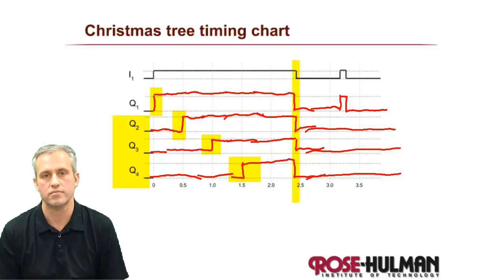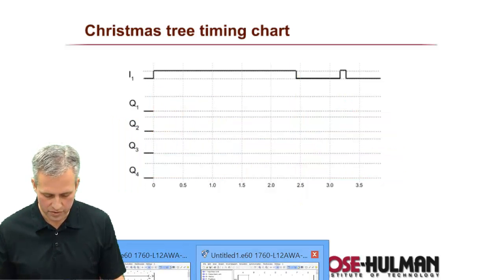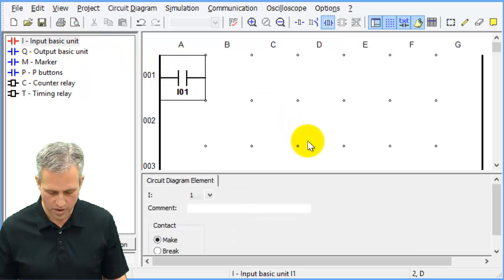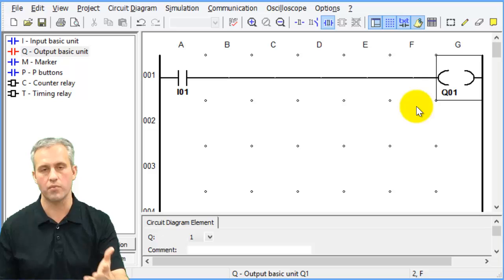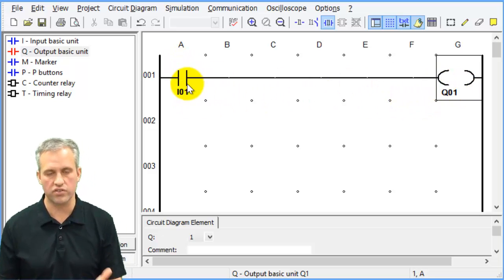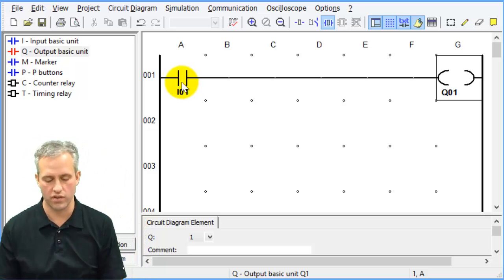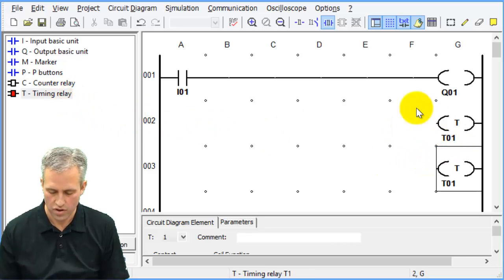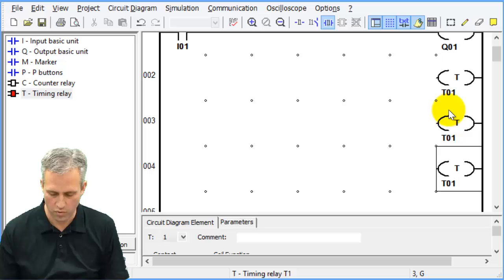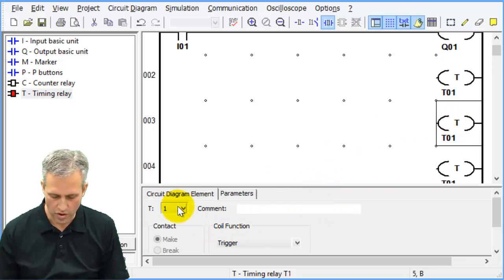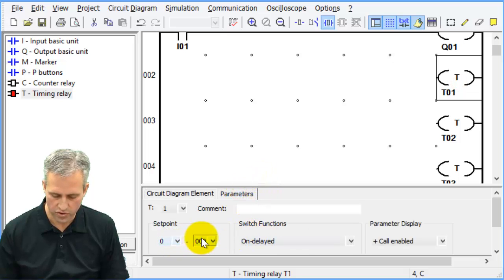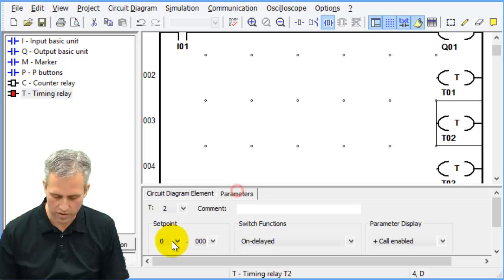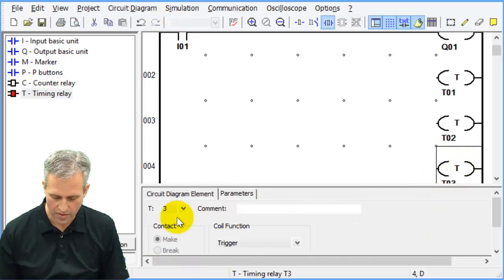Building it in Picosoft: I1 instantly turns on Q1, so a simple contactor works. It also controls three timers — Timer 1, Timer 2, and Timer 3. These will all be on delays. Timer 1 is set to 0.5 seconds, Timer 2 to 1.0 second, and Timer 3 to 1.5 seconds. They all follow the input state.